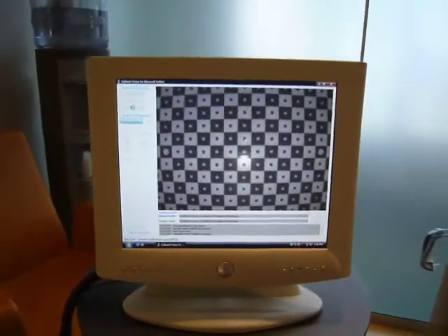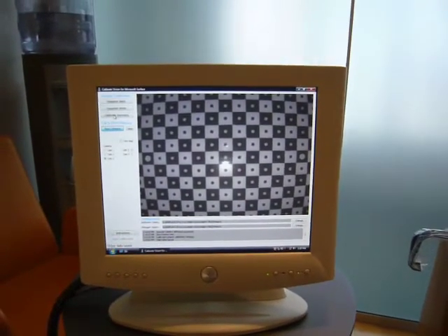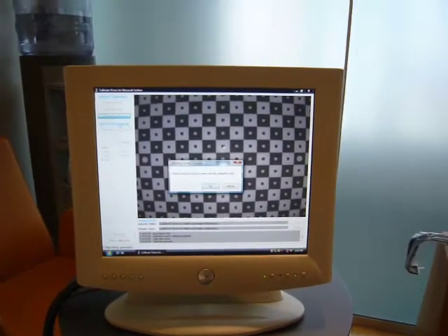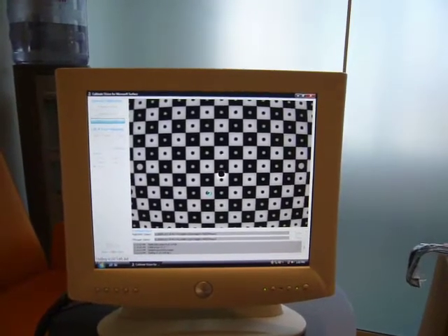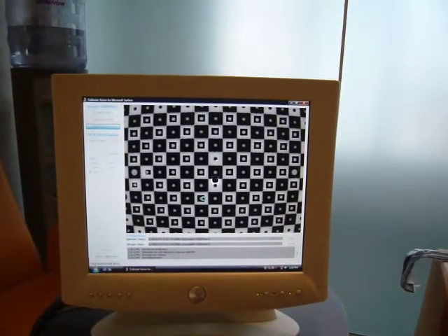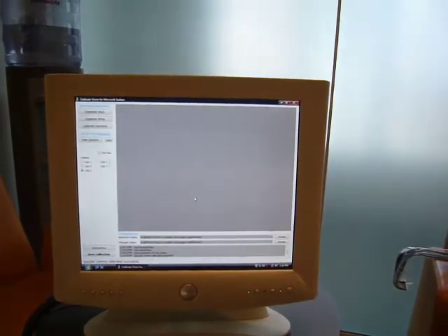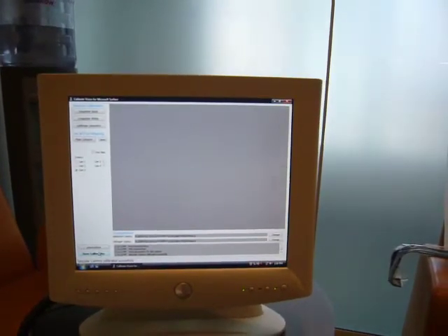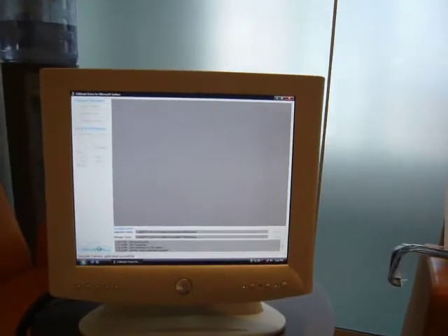And then it tells us that the calibration is complete. Lastly we have to do the final calibration which is the geometry. Once again it has realigned the board, and calibration is now complete.